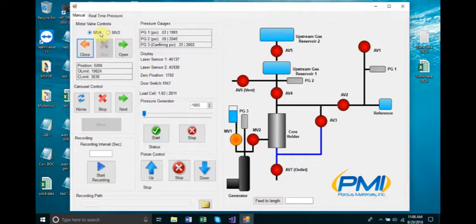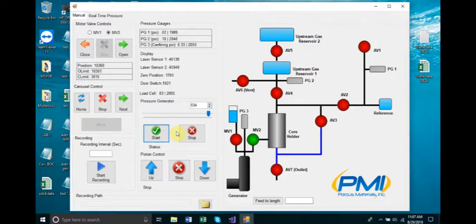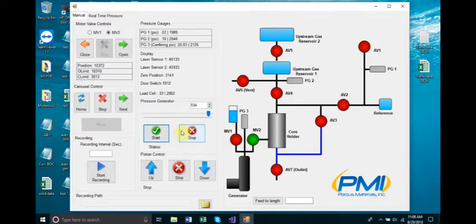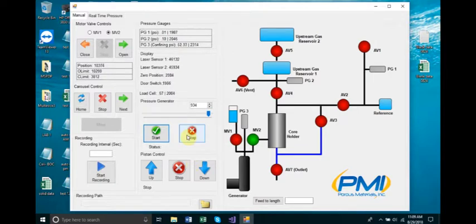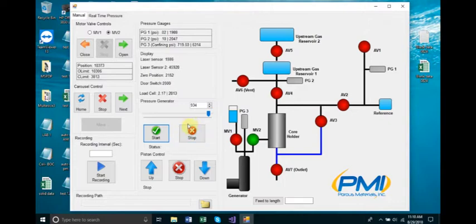Close MV1 and open MV2. Raise the piston of the generator, set a positive value in the slide bar, then click start to deliver water into the core holder. This applies the confining pressure. In the pressure gauges panel, monitor P3 to see confining pressure. Once the target pressure is achieved, stop the generator. If the generator piston reaches the top limit before reaching the target pressure, close MV2 then open MV1, then move the piston down to refill the generator and reapply confining pressure. If the confining pressure drops below the target pressure, raise the piston and rebuild the pressure. Once the confining pressure has stabilized, you may proceed.